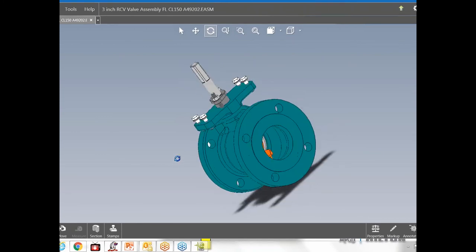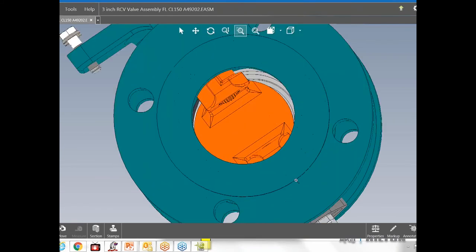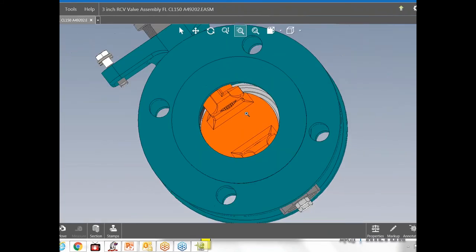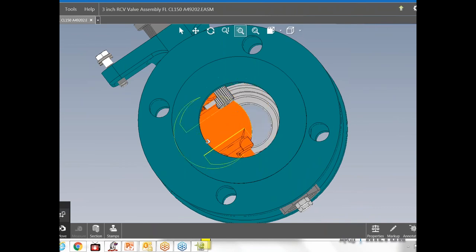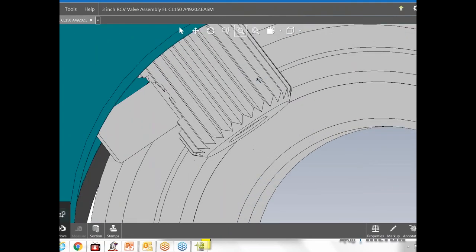I'll turn the valve around. Here you can see on the inside there's no crossover shaft. When the valve is open, you get a clear flow path going all the way through, which is really critical if you want to make sure you get all the capacity available. And if you're flowing a slurry, you don't want anything in the way of the flow stream. There's a blind shaft, and it is also pinned, making a very secure connection with the shaft and the plug. There's no backlash and no slop.